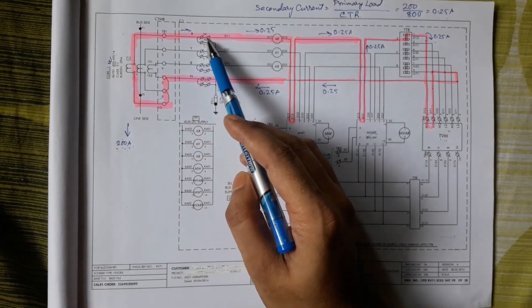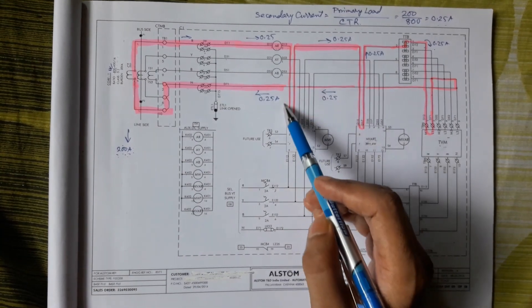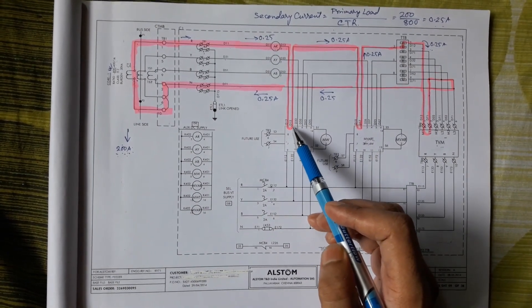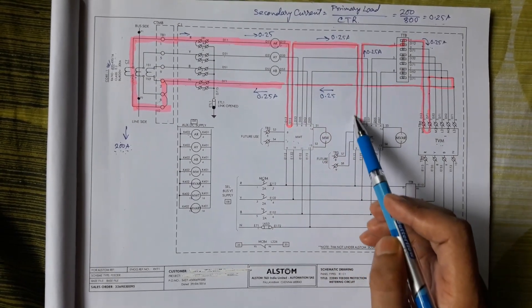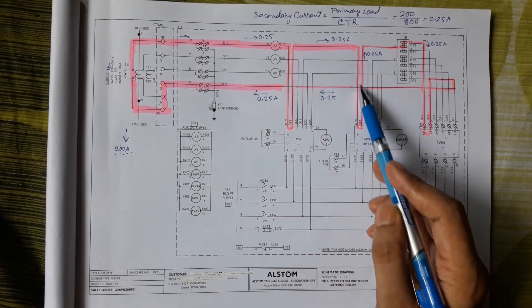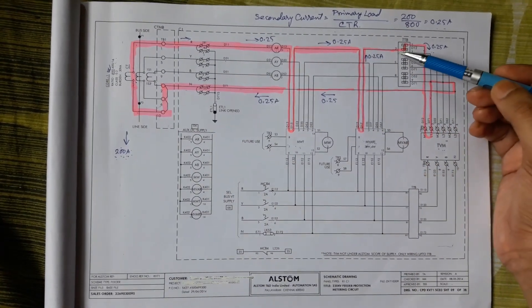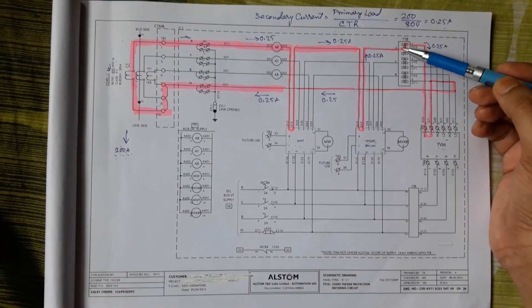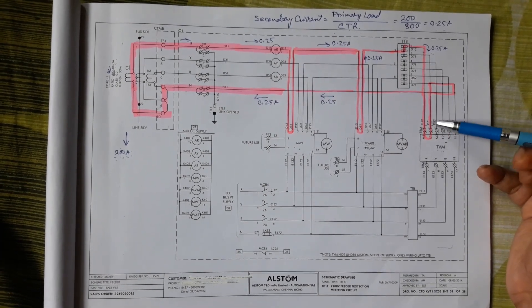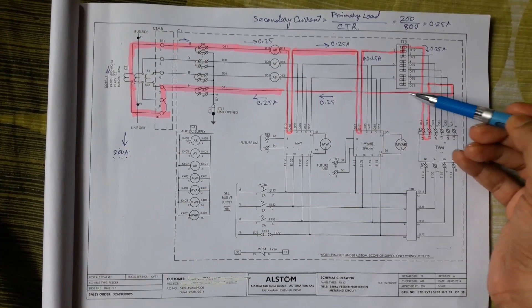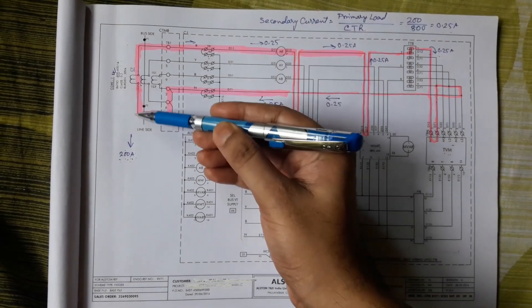The 0.25 ampere will flow through the ammeter first, then go to a megawatt meter, then to a megavar meter, then to a TTB terminal block. If those two terminals are shorted, it will flow through the trivector meter or energy meter and then the current will return to CT secondary in the field.